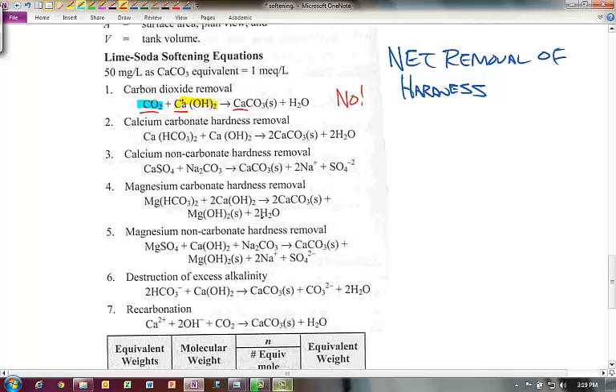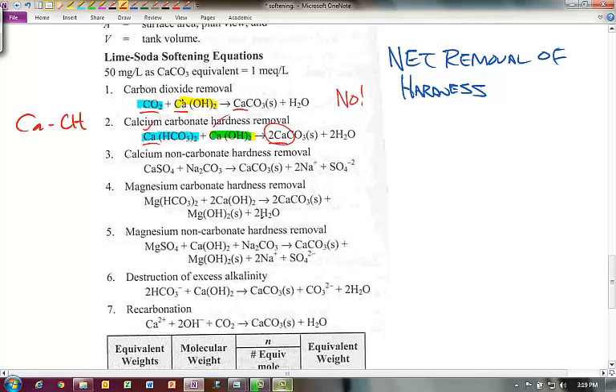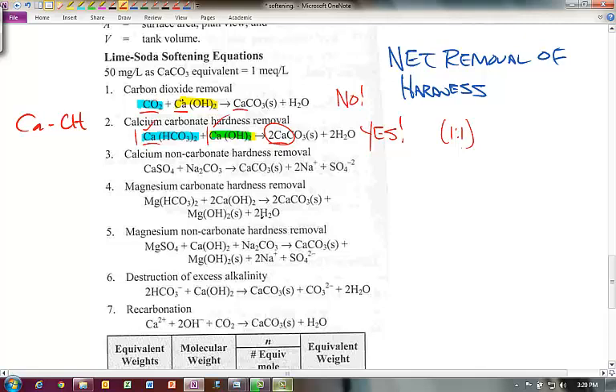Reaction two is calcium carbonate hardness removal. We have calcium in the water, underlined in red, and we add lime into the water. At the end of the day we're removing two calcium: one that was already in the water and one we added, but both are taken out. So yes, there is a net removal. It takes one mole of calcium bicarbonate and one mole of Ca(OH)2 lime slurry to be removed — a one-to-one reaction.